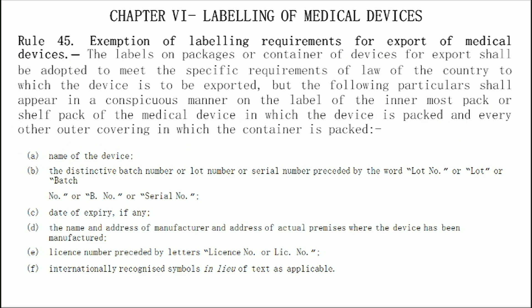For the labeling requirement applicable to export, only certain information has to be mentioned by the applicant, the exporter, on the label of the product which is to be exported: the name of the device, distinct batch number of the device, date of expiry if any, the name and address of the manufacturer and the address of the actual premises where the device is manufactured, license number, and the internationally recognized symbol as applicable. Only that much information has to be mentioned on the label of the product which is to be exported. So these two provisions have been given for the export of medical devices.